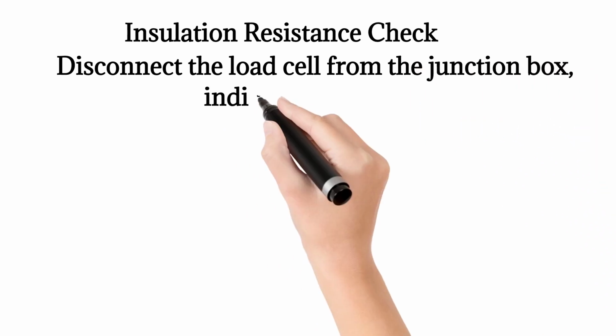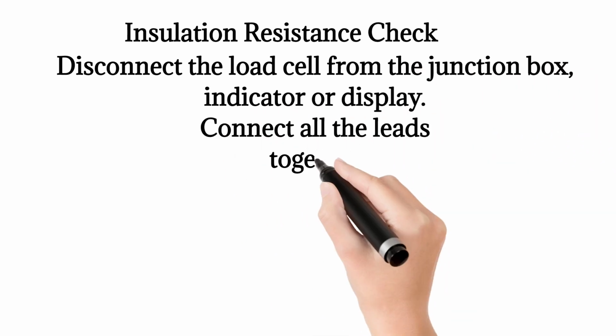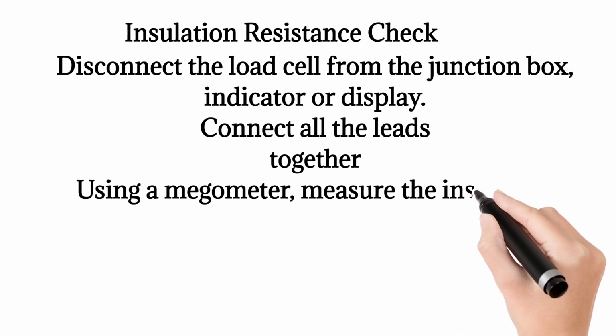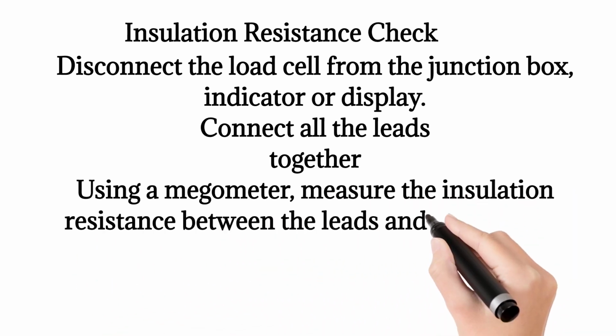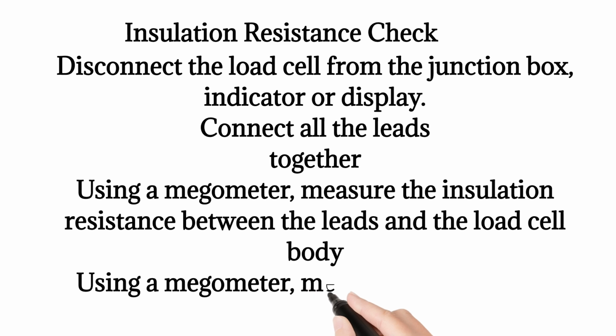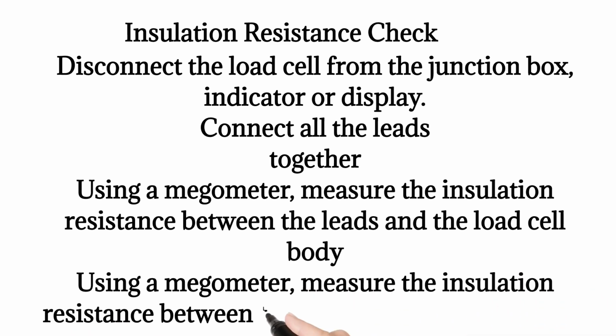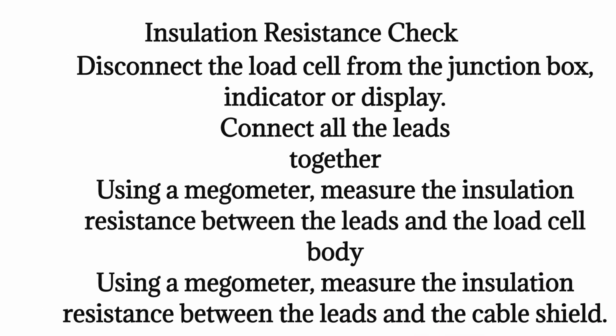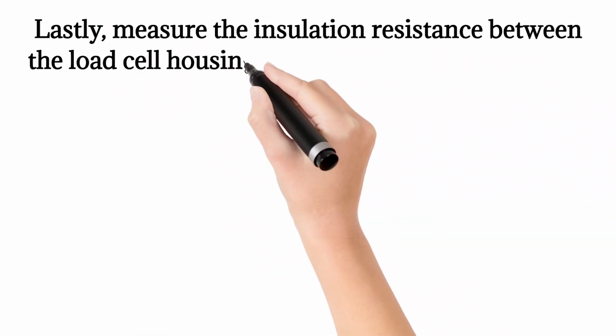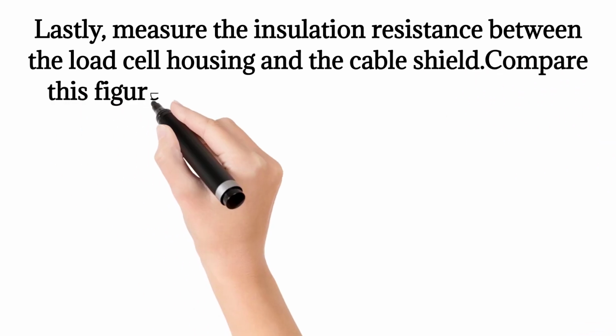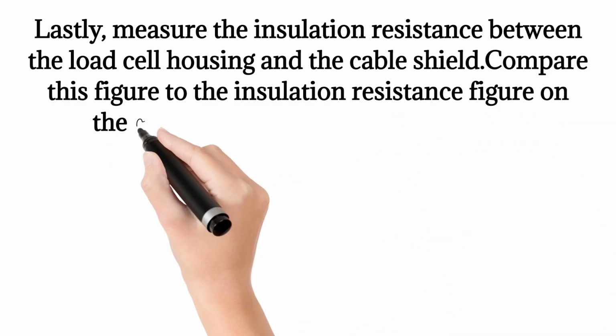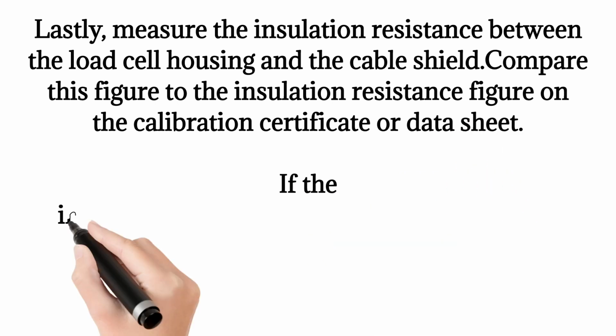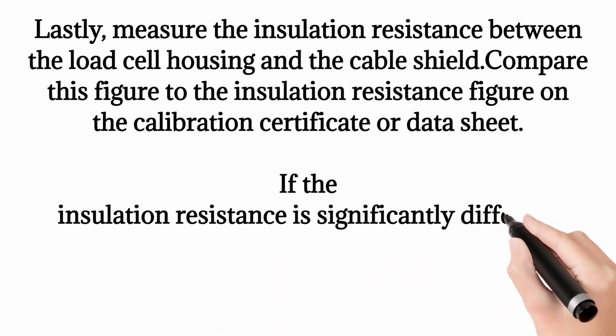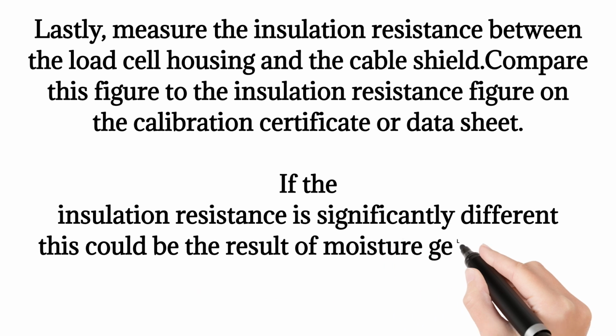Insulation resistance check. Disconnect the load cell from the junction box, indicator or display. Connect all the leads together using a megohmmeter. Measure the insulation resistance between the leads and the load cell body using a megohmmeter. Measure the insulation resistance between the leads and the cable shield. Lastly, measure the insulation resistance between the load cell housing and the cable shield. Compare this figure to the insulation resistance figure on the calibration certificate or data sheet. If the insulation resistance is significantly different, this could be the result of moisture getting inside the load cell.